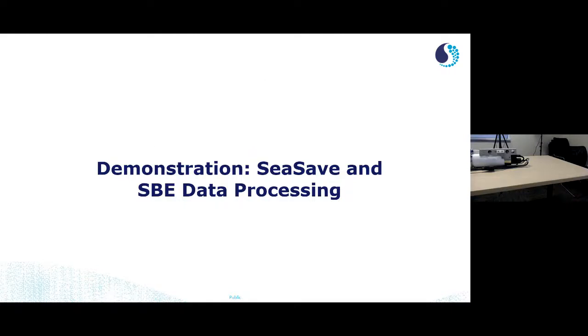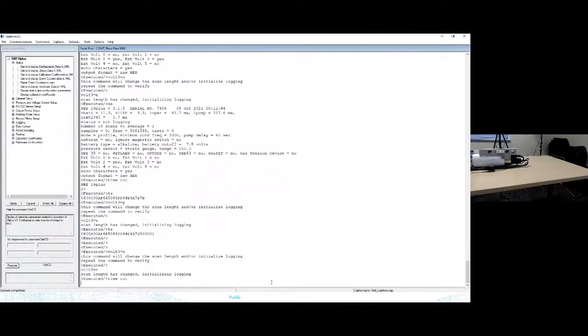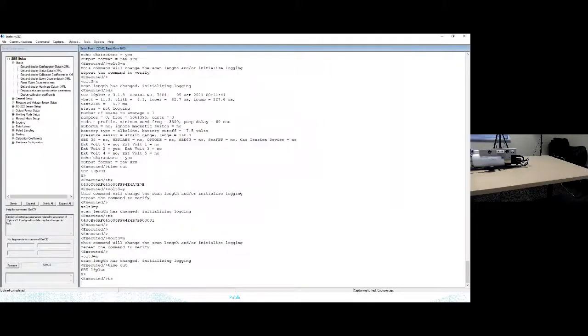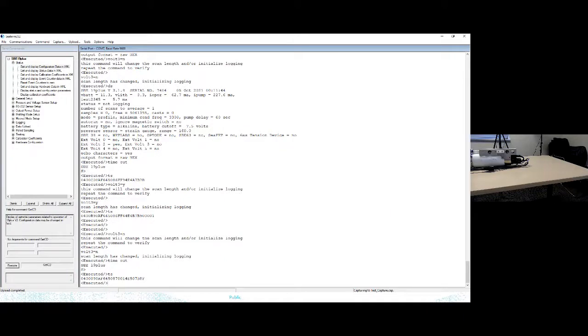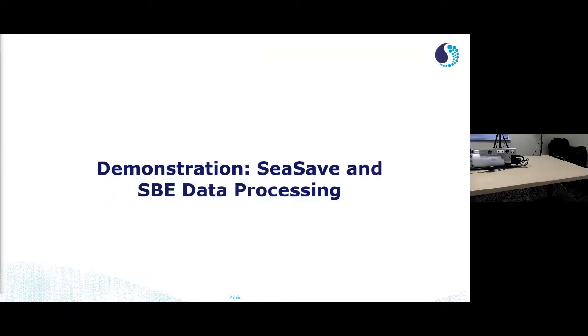So the first thing I'm going to want to do is, in SeaTerm, confirm that I'm outputting raw hexadecimal data, which I am, which is the format that SeaSave requires. After I've done that and confirmed that my voltage channels and everything match up with my configuration file, I'm going to close SeaTerm because it's currently occupying the COM ports, and you can only have one piece of software talking on the COM port at a time.